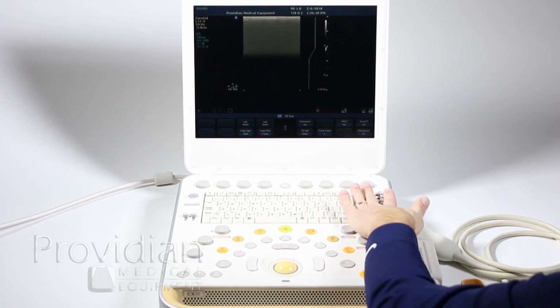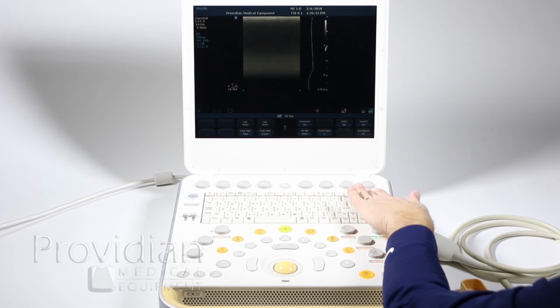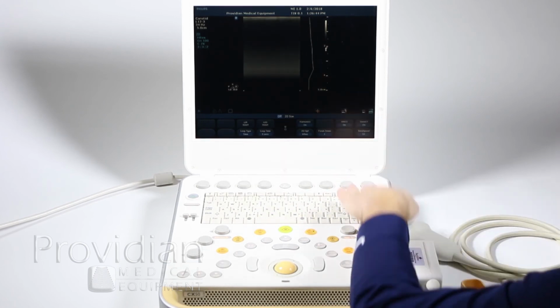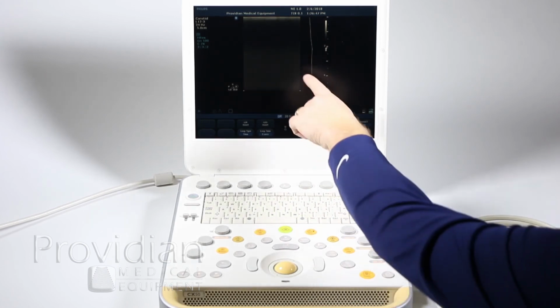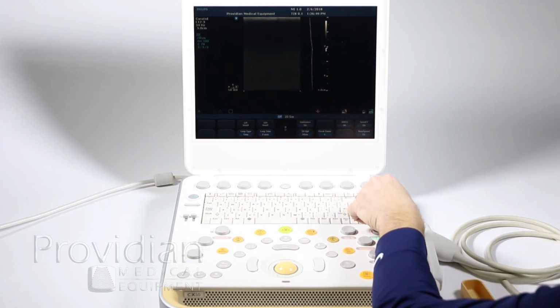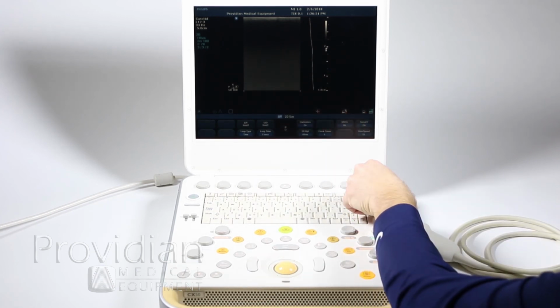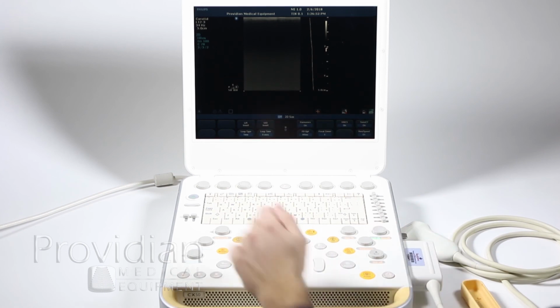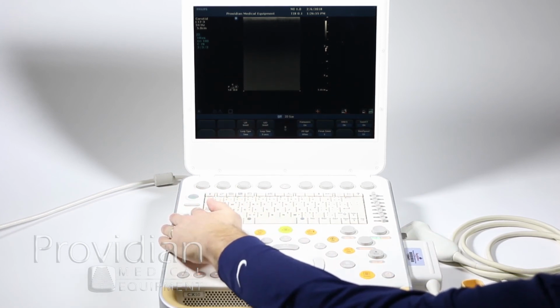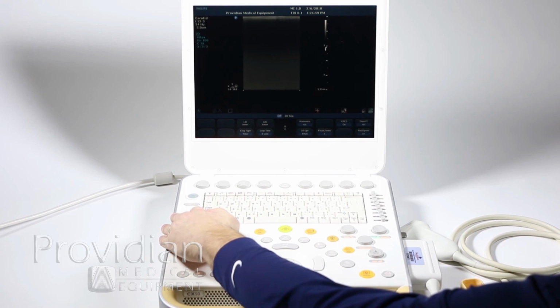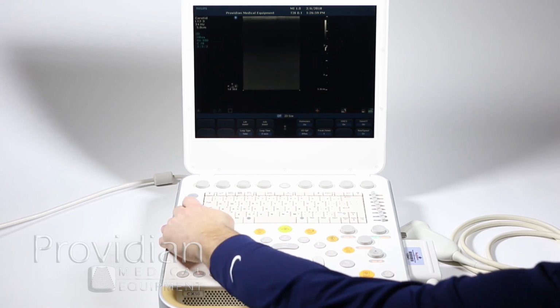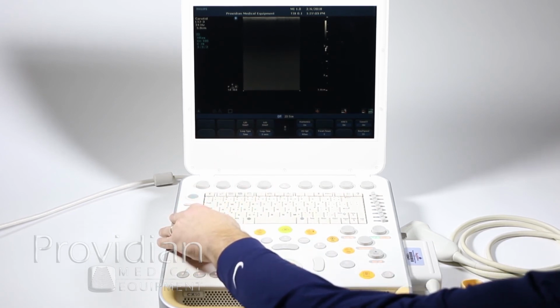I can do that. Typically, you don't need as much gain in the near field, so you'll see this is a little lower, and as your image gets deeper, you'll want to increase the gain to make sure that you can see tissue deeper. You also have your lateral gain controls, which is not something you find on most ultrasound systems, and this is a gain that goes from top to bottom instead of side to side.